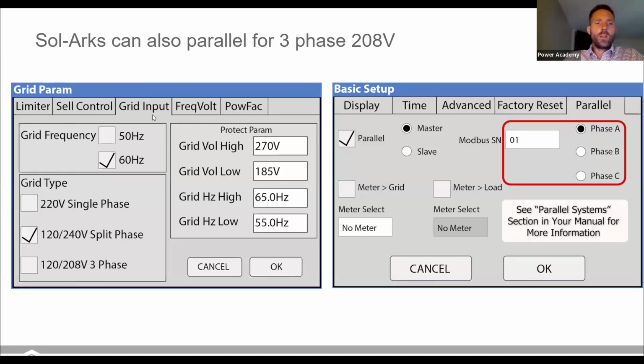Under the grid input here, most common is 120/240 split phase for residential. But as I mentioned, you can easily set this up to do 208 three-phase if you've just got a single inverter.